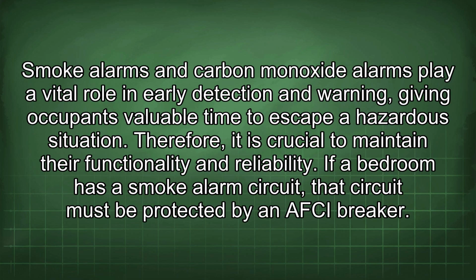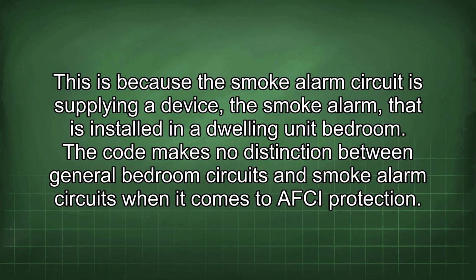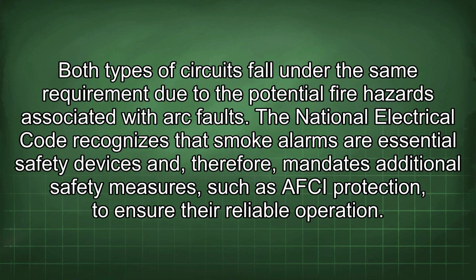Smoke alarms and carbon monoxide alarms play a vital role in early detection and warning, giving occupants valuable time to escape a hazardous situation. Therefore, it is crucial to maintain their functionality and reliability. If a bedroom has a smoke alarm circuit, that circuit must be protected by an AFCI breaker. This is because the smoke alarm circuit is supplying a device, the smoke alarm, that is installed in a dwelling unit bedroom. The code makes no distinction between general bedroom circuits and smoke alarm circuits when it comes to AFCI protection. Both types of circuits fall under the same requirement due to the potential fire hazards associated with arc faults.